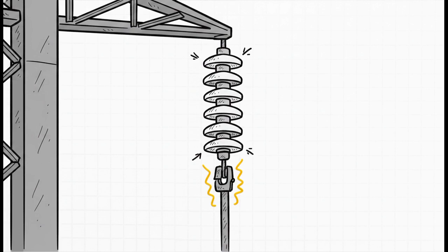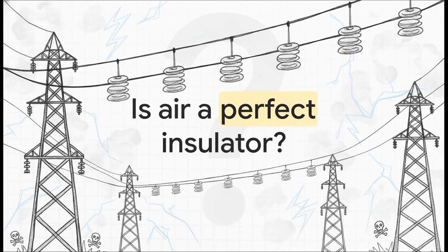Well, the power line flows through a conductor, but right before it reaches the tower, it connects to specially designed massive string insulators. These are usually made of glass, ceramic, or advanced composites. These brilliantly engineered bottlenecks support the staggering weight of the power lines while completely blocking the electricity from flowing into the grounded metal tower.